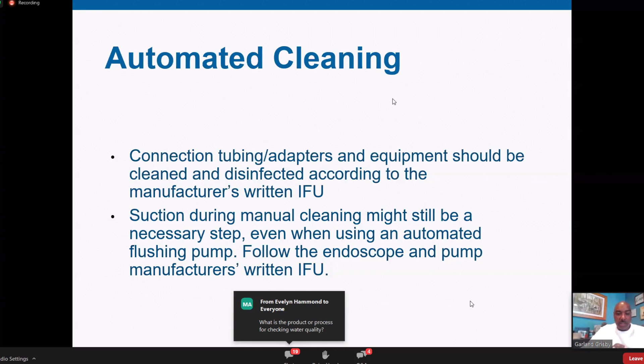Suctioning during the manual cleaning still might be necessary. Again, follow the endoscope and pump manufacturer's written IFU, because you may see some scope manufacturers say the scope needs to be suctioned while your sink or automated cleaning area may do flushing. So follow those and combine for best practice. Next.